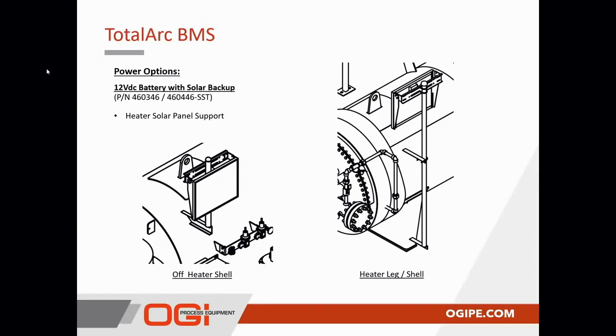Both are intended to allow the heater's solar panels to be rotated 360 degrees to allow them to face the southern sky. Also, these are installed such that there's at least 7 foot of clearance between grade and the bottom of the solar panel. That way we avoid any potential headaches associated with operating these solar panels.